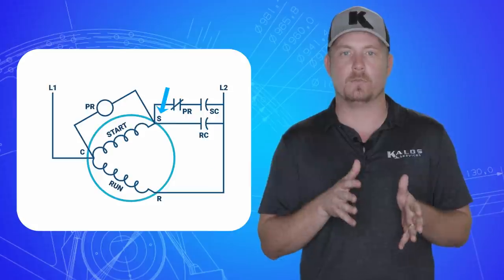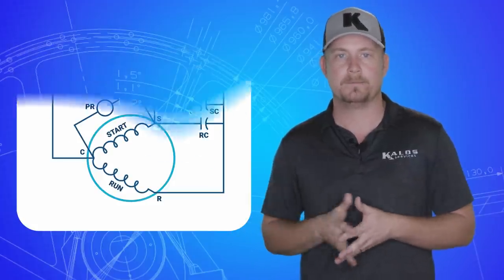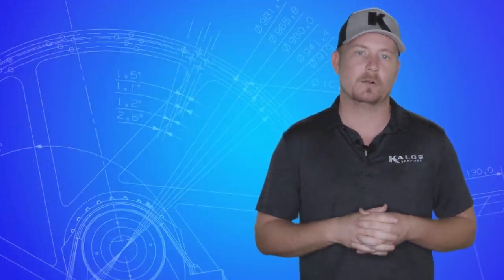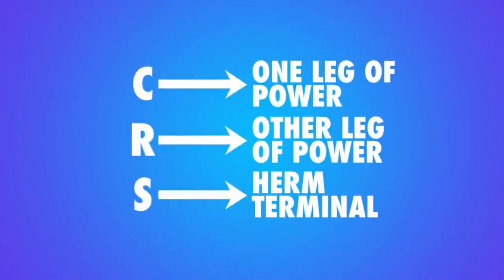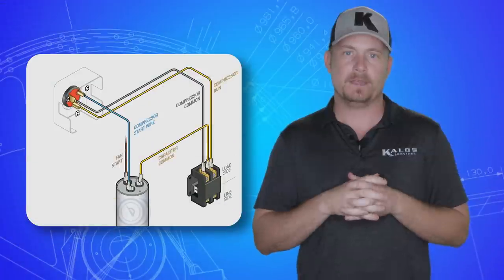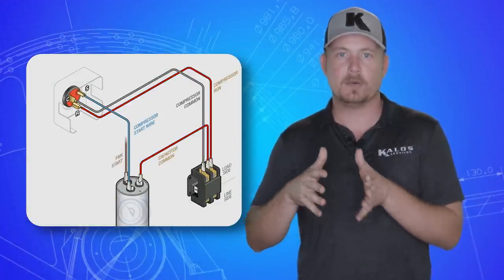So compressor terminals: C goes to one leg of power, R goes to the other, S goes to the Herm terminal on a dual run capacitor with the other side of that capacitor C going to the same leg that feeds R. See what I'm saying? It's confusing.